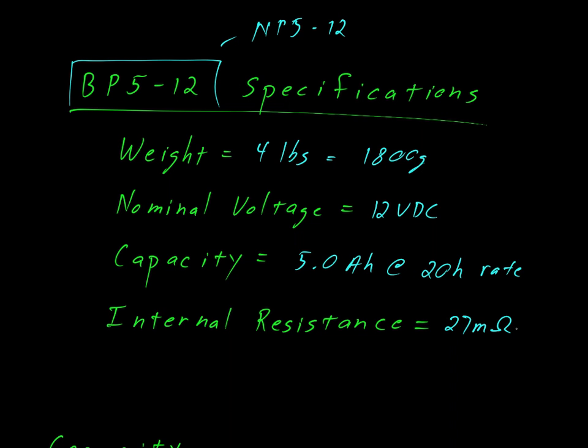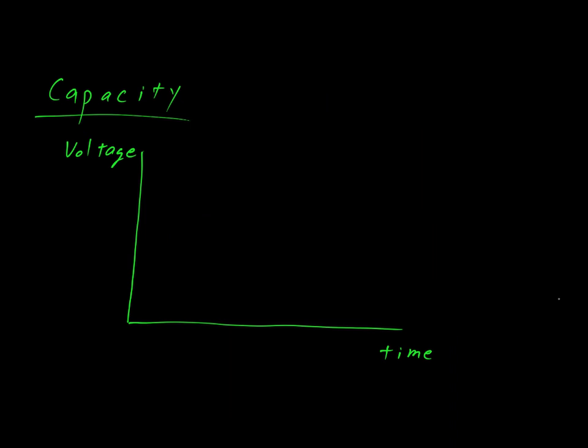To better understand these specifications, let's first look at what we mean by capacity. Here we see a curve where we have time on the horizontal and voltage on the vertical axis. When you first connect the battery up to a load, there will be an initial voltage drop. Then the battery voltage will maintain fairly constant for a period of time, and then it will start to drop at the end. So here we say that 12 volts is the nominal voltage of the battery. That's where it stays for most of its life. And we reach this point here down at 10.5 volts, and we say this is the discharge point for the battery.